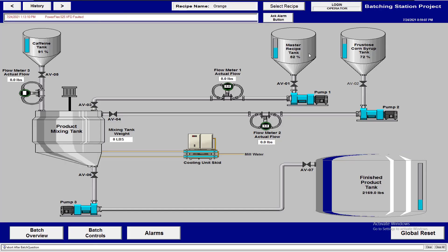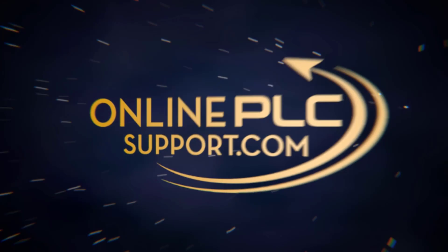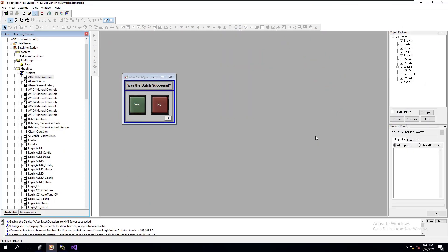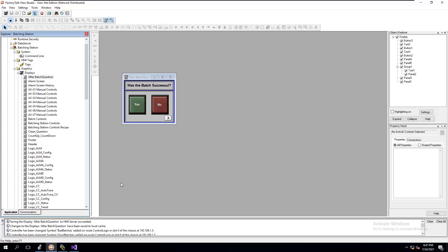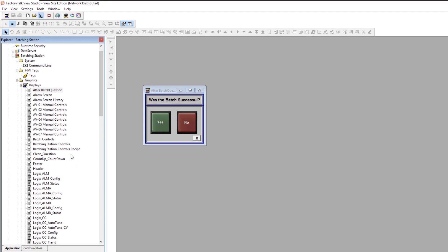The VBA code is what called the screen up. In this video, what we're going to do is a pop-up screen with FactoryTalk SE. We're going to do this with VBA code, so we're going to show you a lot of different things we can do to have the screen pop up from an actual PLC tag. I've added some logic to say when the batch is complete, we should pop up a screen and ask the operator if it was a good batch or a bad batch, and we just count the batches. But we need to understand how to do a pop-up screen on our HMI system.